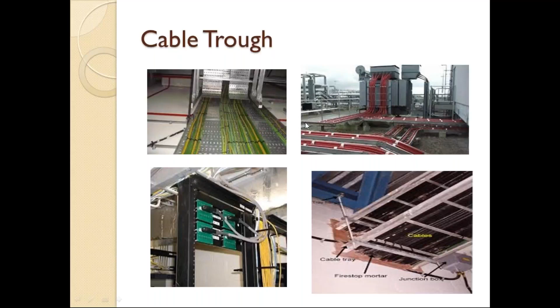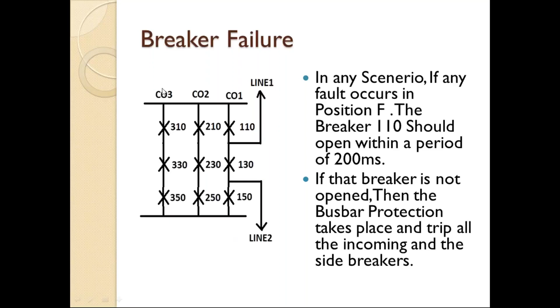This is the breaker failure. There is one concept here: if a fault has occurred and any of the breakers fails to operate, fails to trip, that is the breaker failure. It will wait for some time, and if the breaker still has not operated, then the next breaker will trip, isolate the fault, and protect the remaining equipment. So that is breaker failure, one of the concepts we use in the circuits.